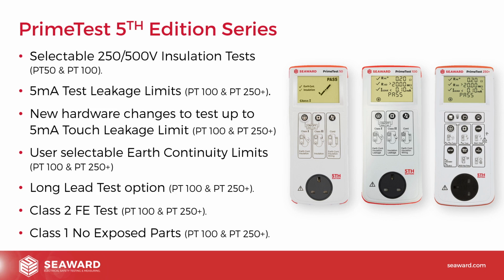User selectable earth continuity limits. Again, on the 250 and 250 Plus and the Prime Test 100, we've actually allowed the user to be able to select from 3 options for the default earth continuity limit. So you can now choose between 0.1 ohms, 0.2 ohms and 0.3 ohms.